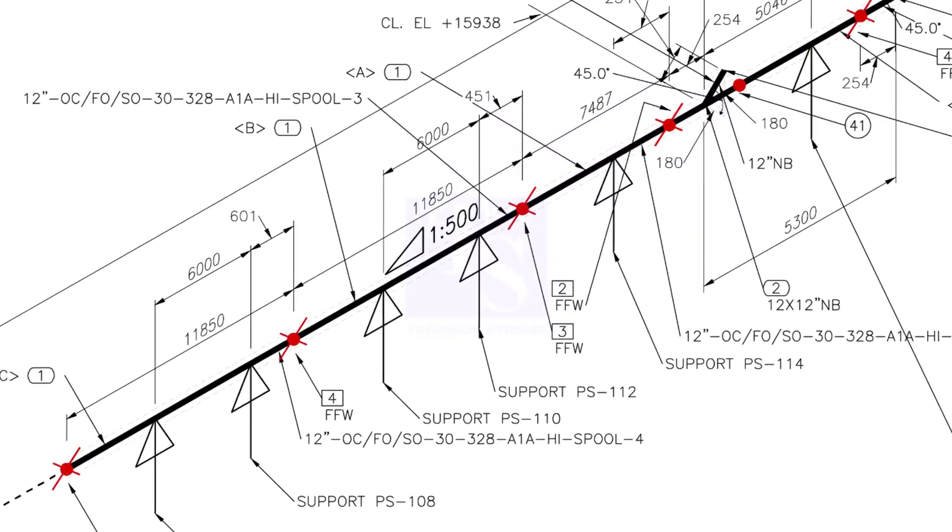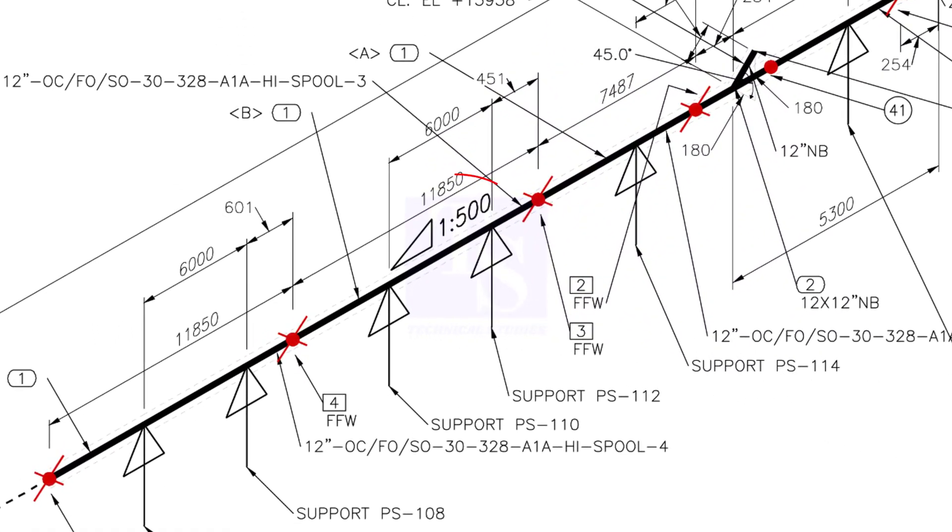The ratio of the slope in this piping is 1 is to 500. Means, in every 500 mm length, one end of the pipe will be lower by 1 mm than the other end.